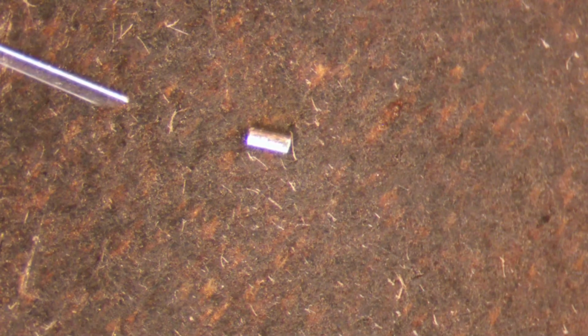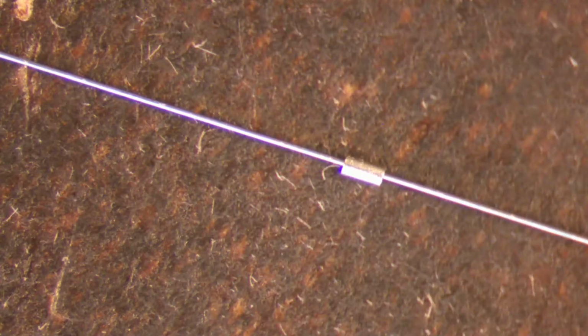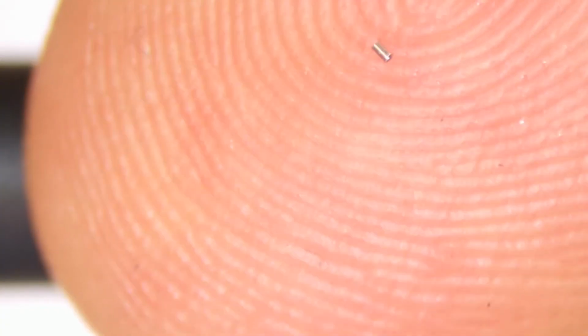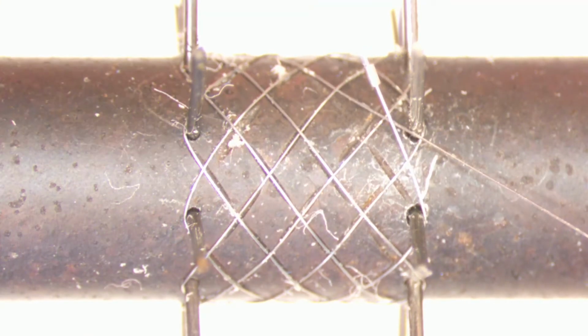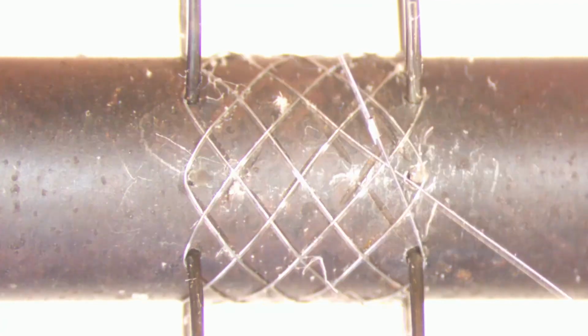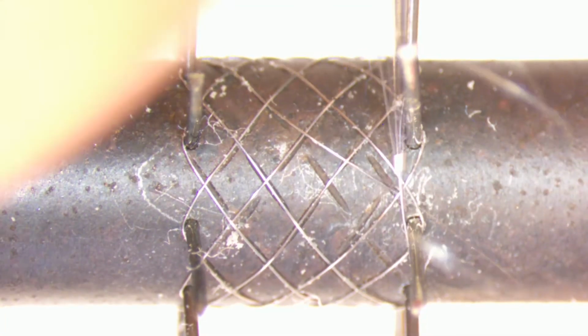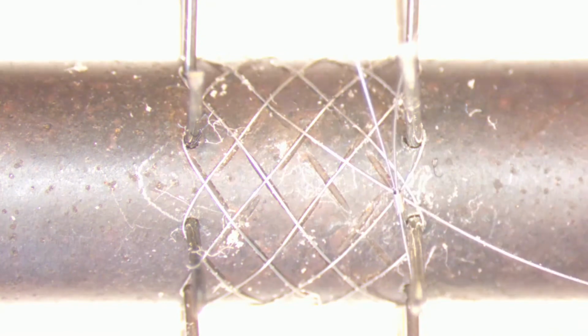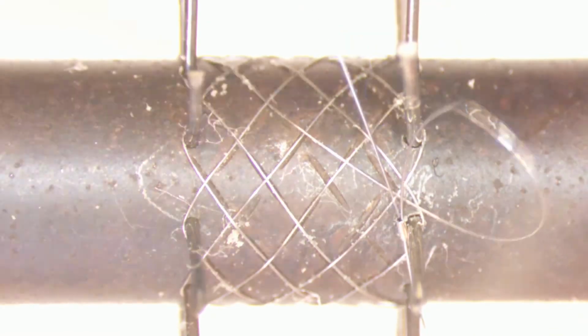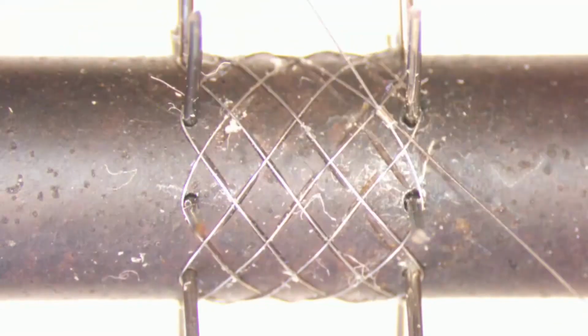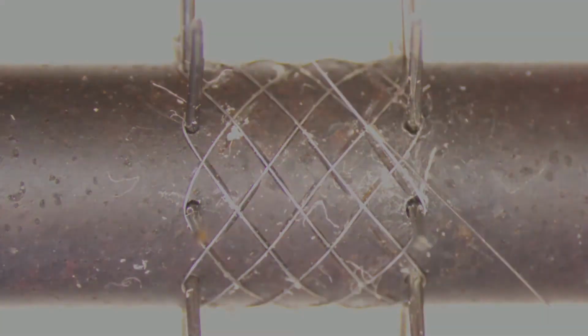Start with taking one end of the wire and push it through the sleeve. This works best if you place the sleeve on your fingertip. Push the marker band further up to the braid. Now take the other wire and thread it through the marker band from the opposite side and tighten the wires. Then squeeze the marker band with a blunt object. You can use a hex key for this, for example. Check that the marker band is tight. Then cut the wire ends with side cutters as close to the marker band as possible.